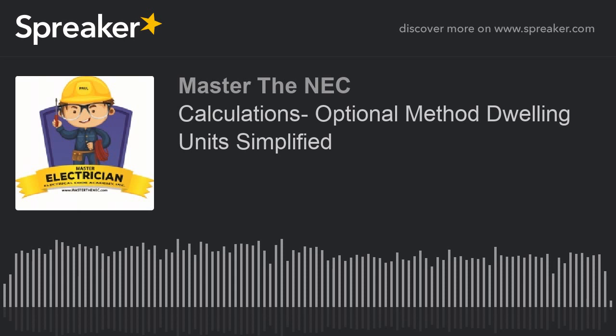7,613. So I could really stop there. I could know that the AC is going to be larger. But if you wanted to work it all the way down, the 6,667 times 65% is 4,334. So I'm omitting the heat. I'm going to stick with the AC in this case. But remember, there's a bunch of different options here.